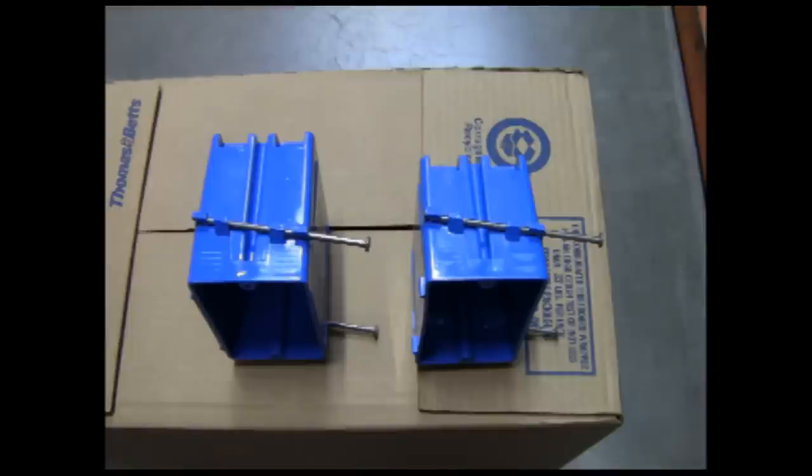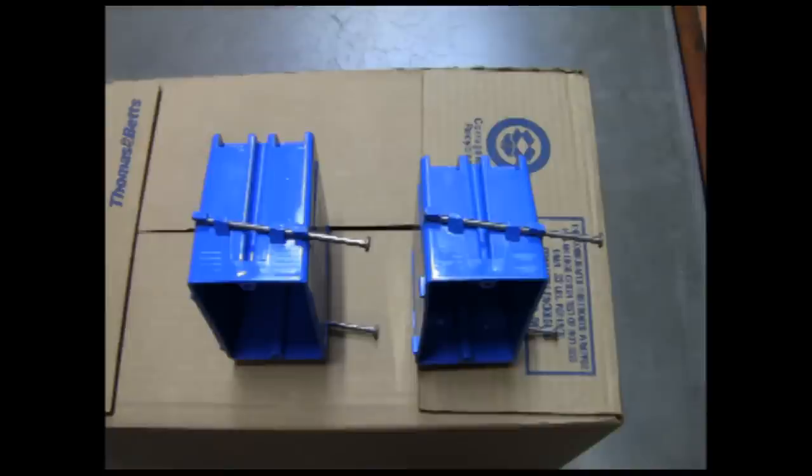Generally they come in two depths, standard and deep, as shown by the two boxes. All boxes are rated for the size and the amount of wires that can be pulled into them. This rating is almost always at the back of the box. The deep box has more cubic inches, so it's rated to contain more wires.